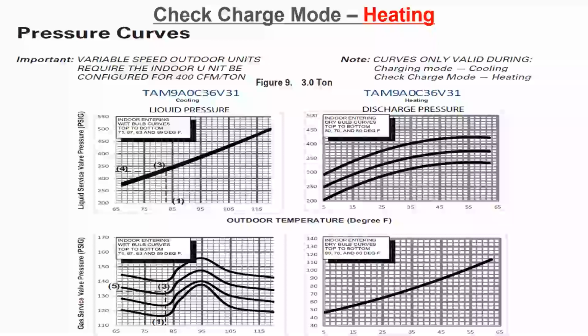In October, I'm going to have another quick hitter that we're going to dive deeper into the heating side of it. Right now, we're going into the cooling season, so we're going to be charging per subcooling, which is the 10 degree subcool. Always check your data plate. But for check charge mode heating, we're going to go off of the pressure curves.